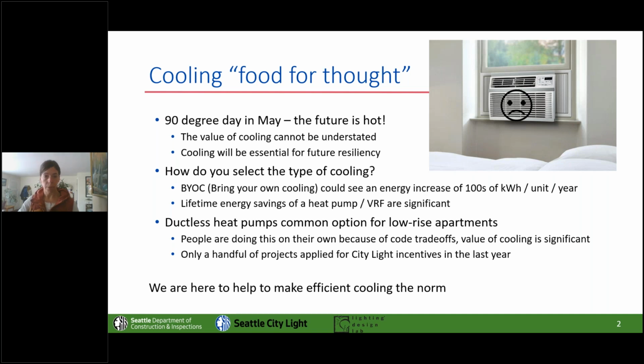Additionally, installing a heat pump or a variable refrigerant flow system could provide a lot of lifetime energy savings per unit compared to just one of these inefficient window shakers. And what we're seeing is the market is really moving towards ductless heat pumps, especially for low-rise multifamily units. And this is something that's happening without Seattle City Light intervention. We're only seeing a handful of multifamily projects coming in our custom program in this last year. But we're here to help. We want to make efficient cooling the norm for multifamily in all sizes of buildings, and excited to talk to you about some options for helping you move towards efficient cooling.